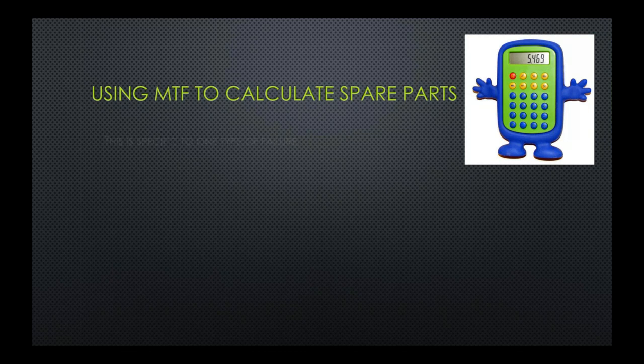So one of the biggest things you have to realize is that this calculation is specific to one specific failure of a device. An easy one to use is an X-ray tube on any device that has an X-ray tube—we can tell if we need to have a spare X-ray tube available. It could be a power supply. It can be any part of a bigger unit.